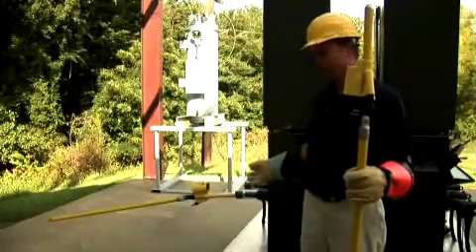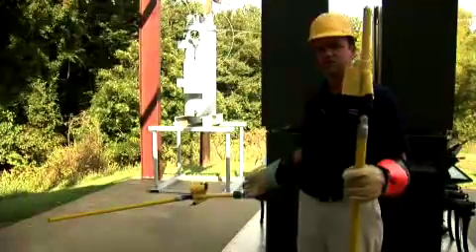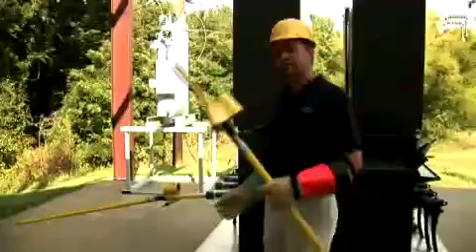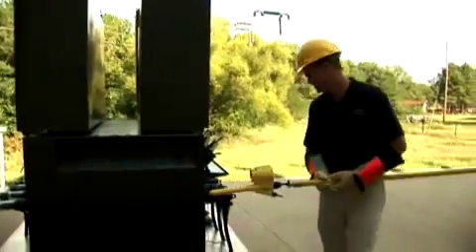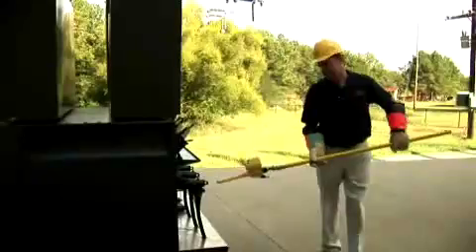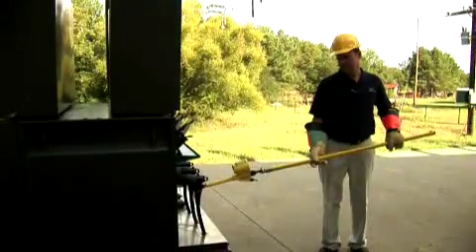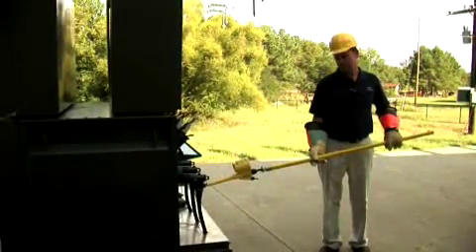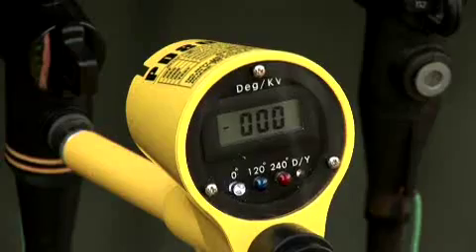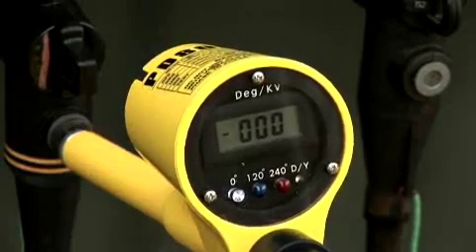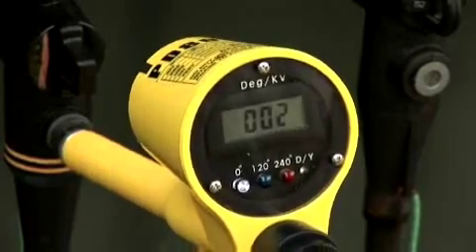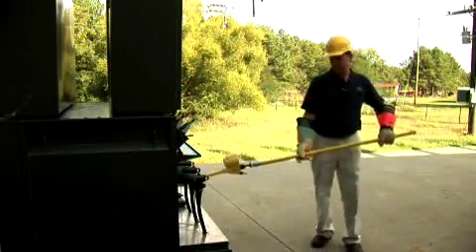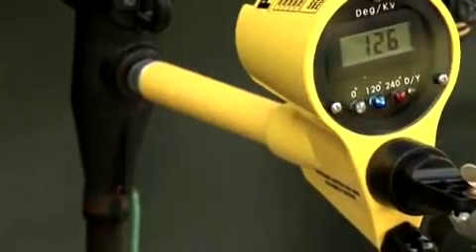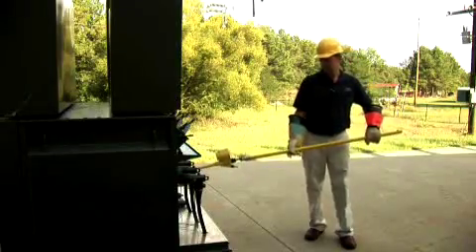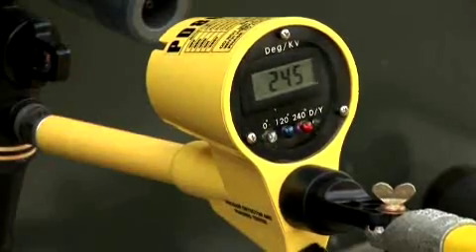Okay, this is a PD800W. I have the reference probe in the degree position on primary voltage. I'm now going to come to the other side of the switching cabinet with the meter probe in the degree position and demonstrate phasing to capacitive test points from primary voltage. Give A phase a white light, B phase a blue light, and C phase a red light.